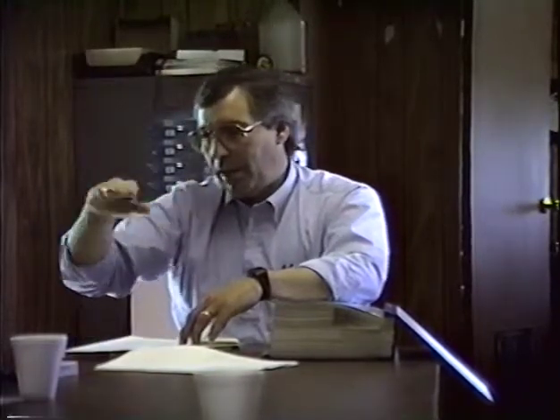It doesn't stay that way, it gets dirty. The permeability of these bags is probably somewhere in the neighborhood of 30 cubic feet of air at a half inch pressure drop, brand new. Well, that volume at the same pressure drop comes down once they get dirty, and then what you want it to do is level out. When it gets down in the range of 1 or 2 cubic feet of air versus the new of 30, and not at the level of 4, 5, or 6, and it's down into 1 or 2, then it's pretty much dead in the water.